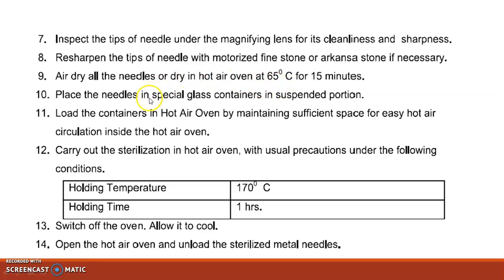Place the needles in a special glass container in suspended position. Load the container in the hot air oven, maintaining sufficient space for easy hot air circulation inside the hot air oven. Carry out the sterilization in the hot air oven with usual precautions under the following conditions. In the oven, we are going to maintain a temperature of 170 degrees Celsius and a holding time of 1 hour. Once this condition is achieved, switch off the oven and allow it to cool. Now open the hot air oven and unload the sterilized metal.